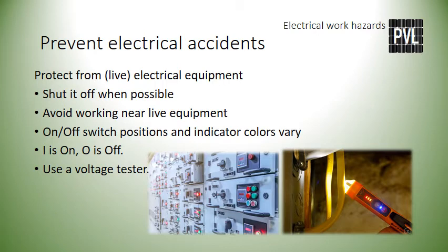Electrical equipment that is accessible may be energized — ensure it is not live before working on it. If working on live equipment is absolutely necessary, the proper PPE will be necessary. At times it is more cumbersome and time-consuming to don the appropriate PPE than to just shut off and lock the power. For example, to safely work on an electrical component of over 50 volts, you are required to wear rubber insulated gloves with cloth inserts and leather gloves.